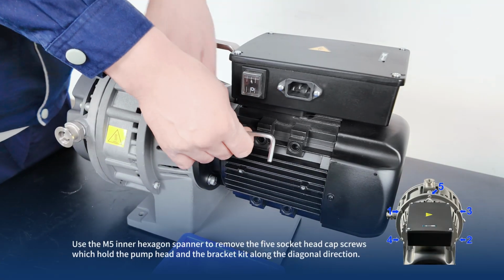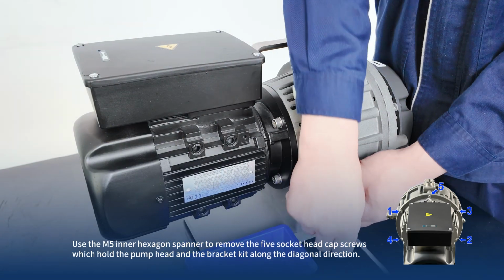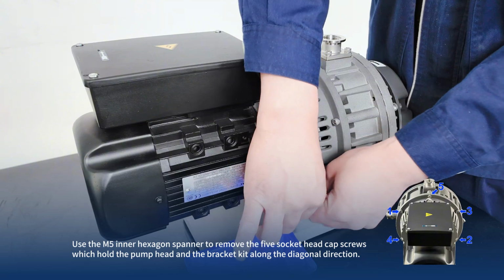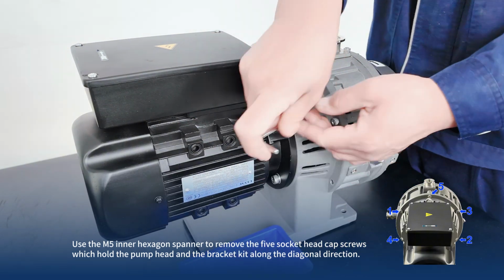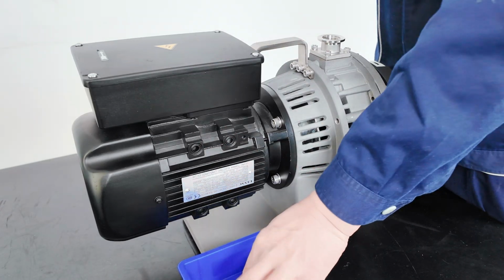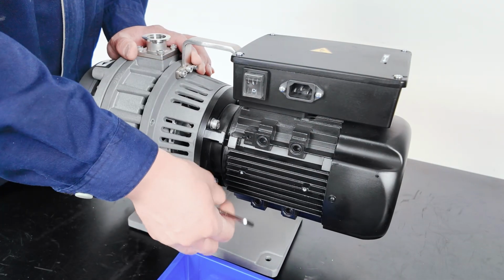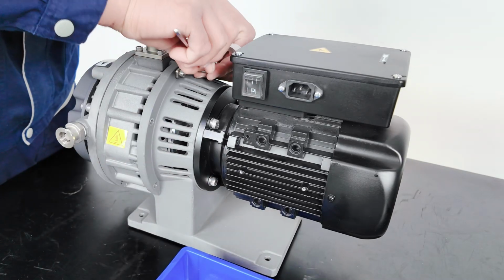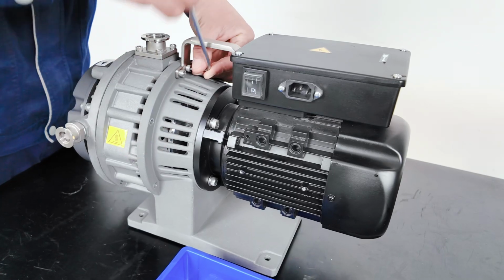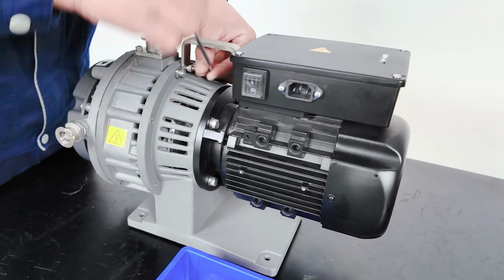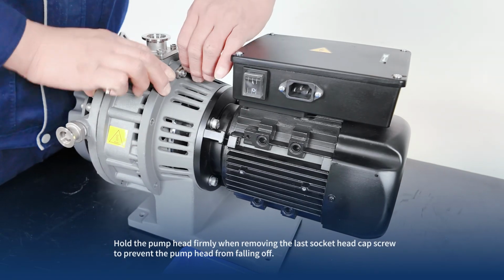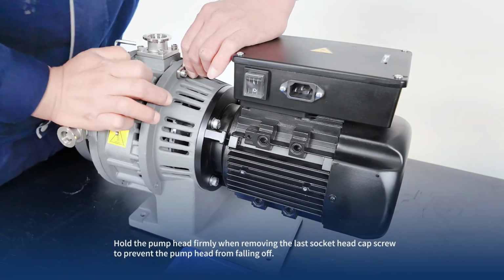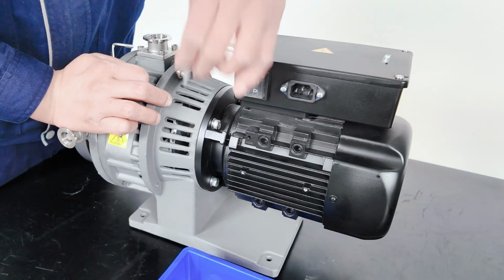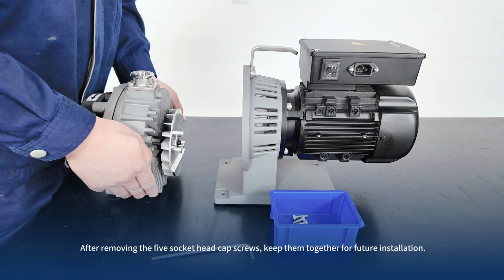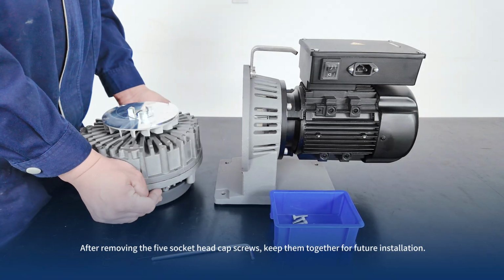Part 2 Repair procedure. Use the M5 inner hexagon spanner to remove the 5 socket head cap screws, which hold the pump head and the bracket kit along the diagonal direction. Hold the pump head firmly when removing the last socket head cap screw, to prevent the pump head from falling off. After removing the 5 socket head cap screws, keep them together for future installation.